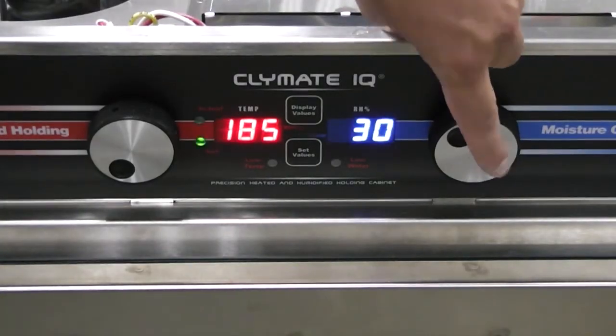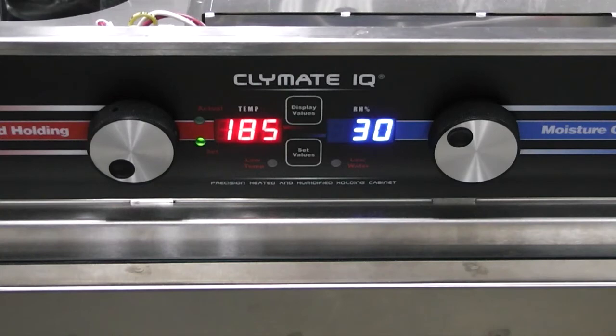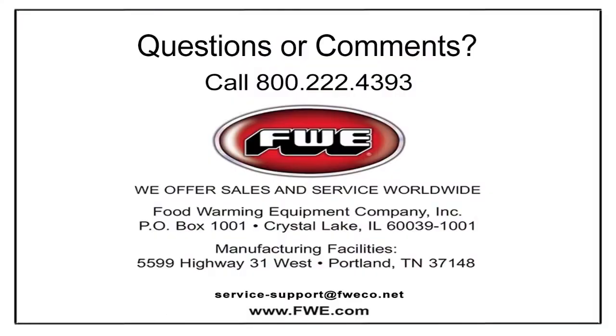Pressing the right encoder after the end of the last parameter will turn all relays off and exit service and diagnostic mode, displaying set point values for 3 to 5 seconds before reverting back to normal operations. If you have any questions, please contact our service department.